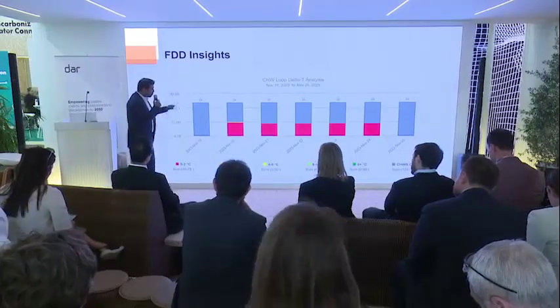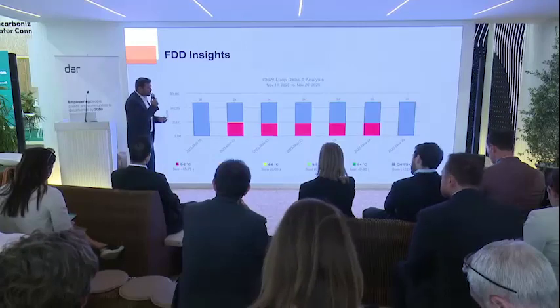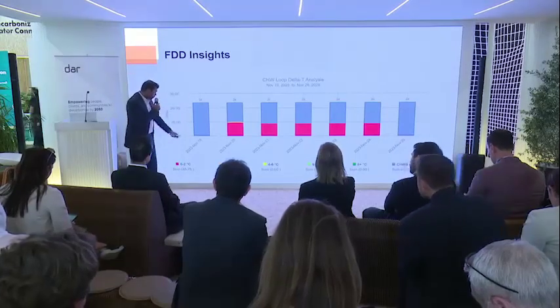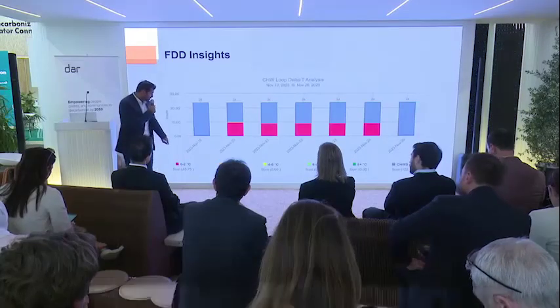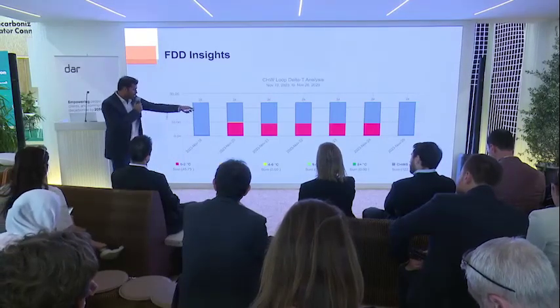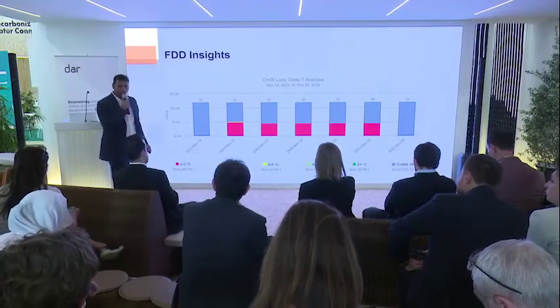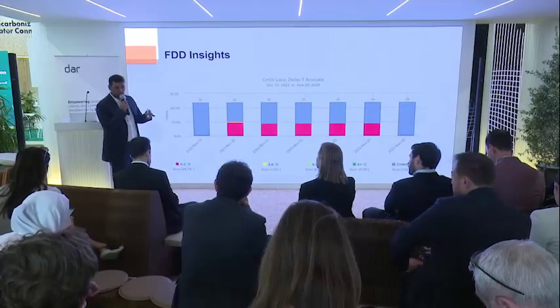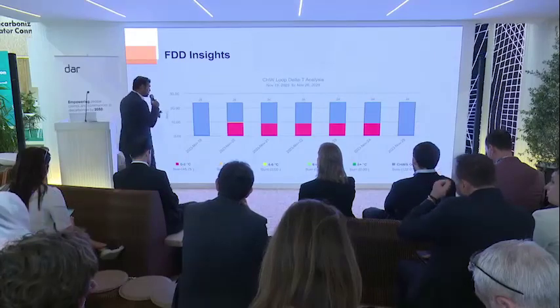So in terms of reporting, analyzing just one chill water loop, what you have here is delta T being calculated. We have different bins, 0 to 2 degrees Celsius, 2 to 4, 4 to 6, and so on. We also have a bin which tracks hours when the chiller or the chill water system was turned off completely. And this is the interesting part.